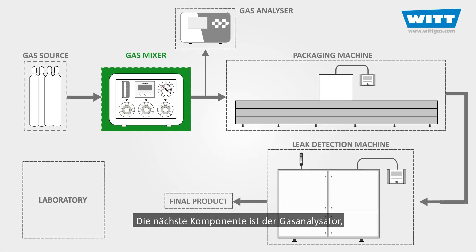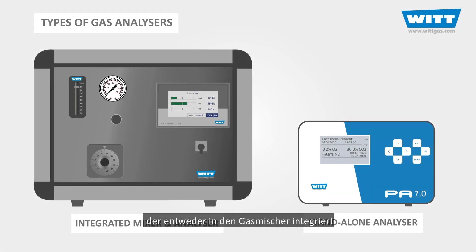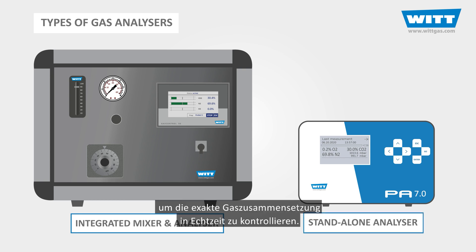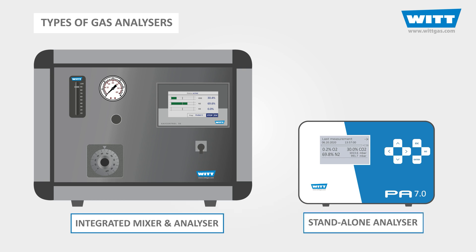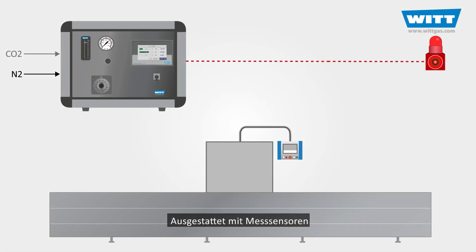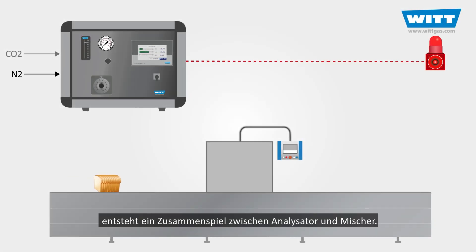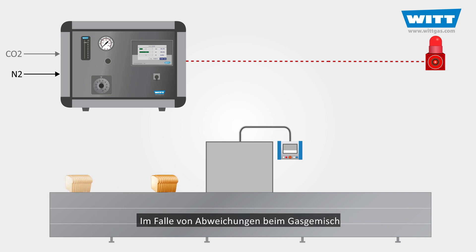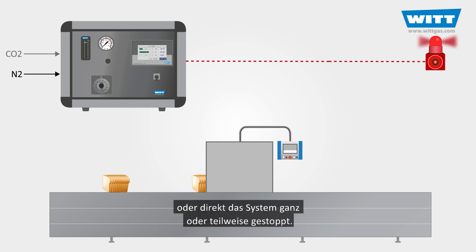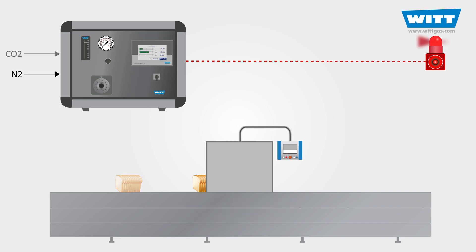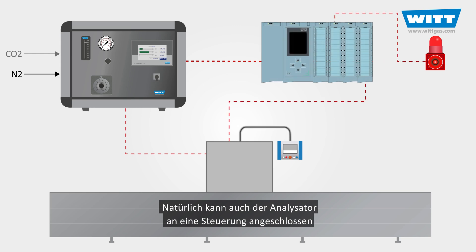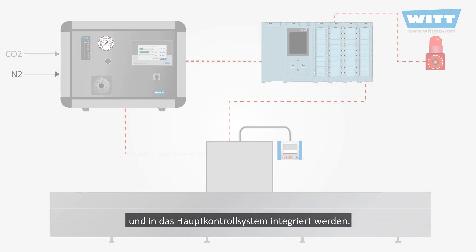The next component is the gas analyzer, which could be integrated into the gas mixer, or could be a standalone unit for monitoring the exact real-time percentages of the gases. Equipped with measurement sensors, the analyzer will work in conjunction with the mixer, and in case of any anomalies in the gas mixture, it will inform the operator by activating an alarm, or will directly shut down the whole or a specific part of the system. Of course, the analyzer can be connected to a PLC as well and be integrated into the main control system.